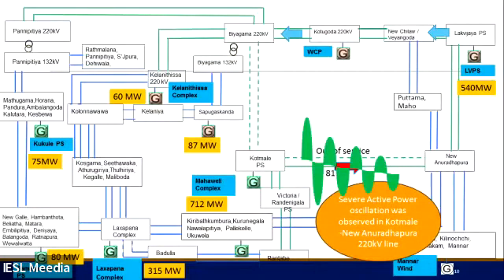So what we have experienced, we have never experienced that one. Severe active power oscillation was observed in the Kotmale New Anuradhapura 220 kV line. At the same time, we observed an over frequency condition in Kotmale, because it loses 720 megawatt of generation. I mean, there's no path to deliver the 720 megawatt of generation. So that bus experiences an over frequency condition.